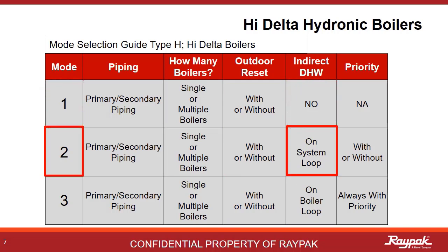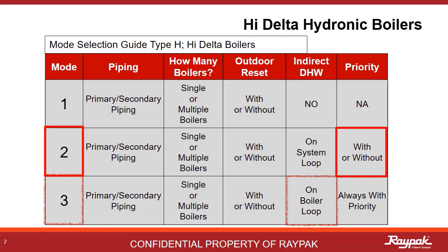If there is an indirect system present on the system loop, then it is Mode 2. If the indirect is present on the boiler loop, then it is Mode 3. Mode 2 can be run with or without priority, while Mode 3 is always with priority.